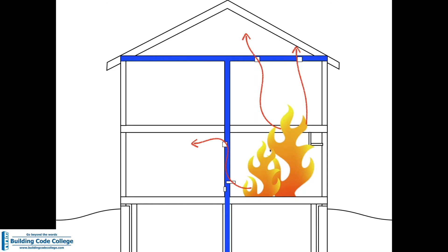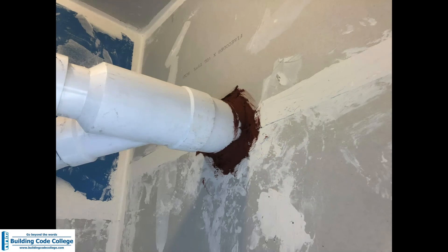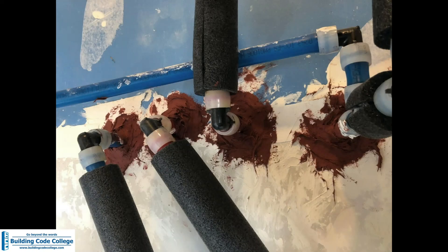You still need electrical outlets and plumbing in walls, so you have to put the holes there — but you have to protect the holes. That's what a fire stop system does. People often hear 'fire caulk' and treat it as a magical solution to any hole in a rated wall. With a plastic pipe going through a rated wall, in a fire situation the plastic melts out and you'd be left with a big hole. The idea of fire stopping is that the material expands, hardens, and fills the hole under fire conditions. There are serious nuances to how you install fire stopping so that it actually works as intended.